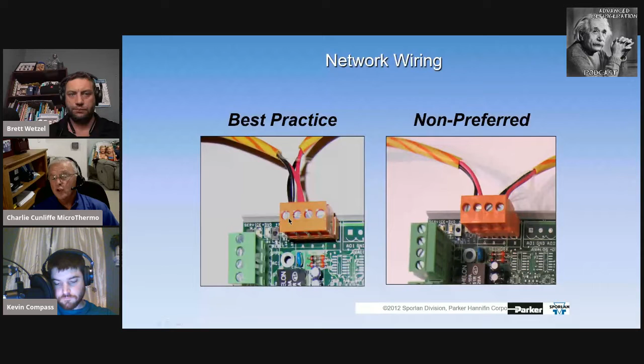If you wire it this way, if I have a problem with the node or I unplug it, I've now interrupted the network. So we try to preach that, but after a while we just said, well, we've got to do away with the 4-lug, and all of the new boards only have 2 lugs on them, so you can't make this mistake.